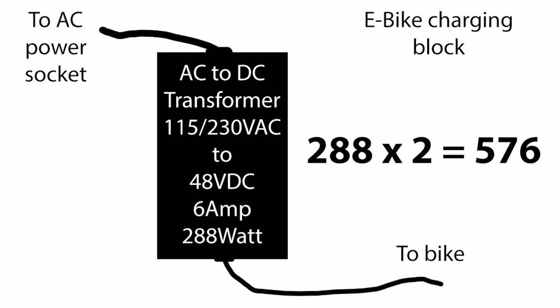In this example, I'm going to look to charge up 2 electric e-bikes that use an intermediary AC transformer charging block, like what we might use in a regular building. We need to look for a label on the charging blocks that gives us the wattage at maximum draw. As it is, both the charging blocks indicate that they will charge the bicycles at a rate of 48 volts at 6 amps maximum, which calculates to 288 watts each charger running at maximum charge. That's 6 times 48 equals 288.